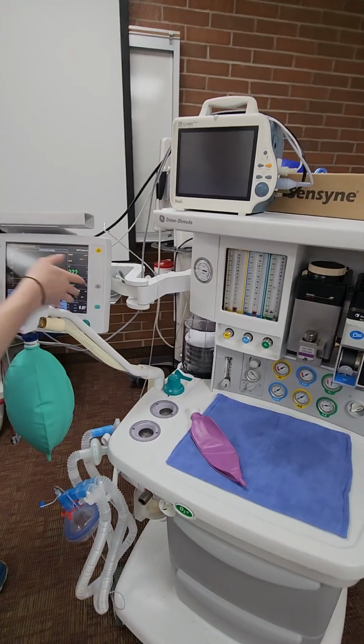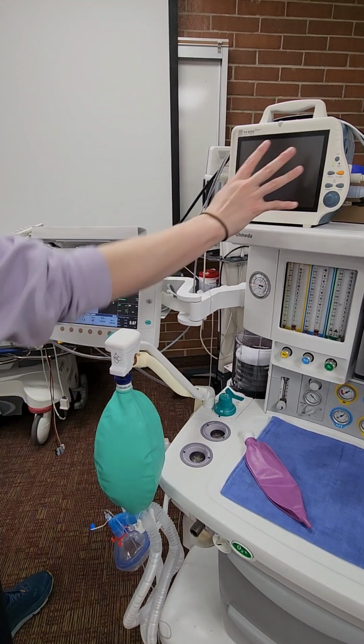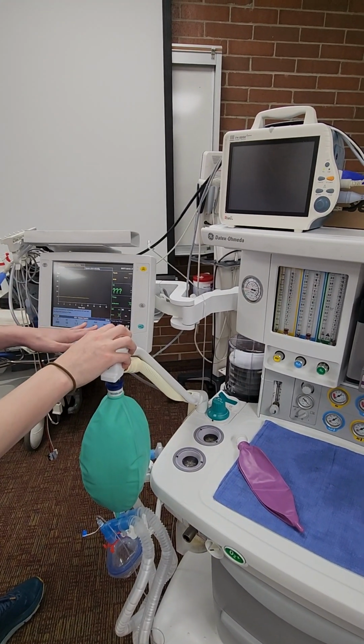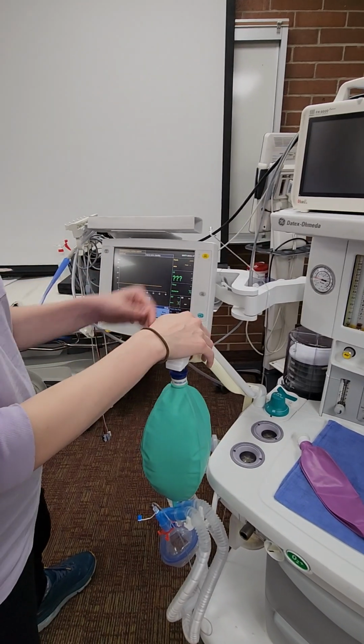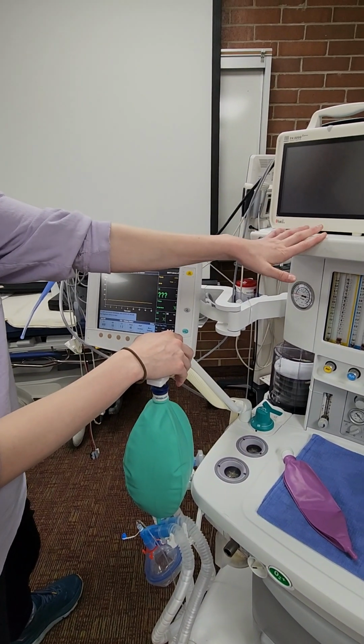Looks like your machines are on. Now you can, this one's on too, you can check the parameters, make sure all of the parameters that you set you're comfortable with, that's what the plan is. Make sure your patient monitors are gonna go off, make sure these alarms are going to alarm. And now you're ready to check your circuit. So you're over here.